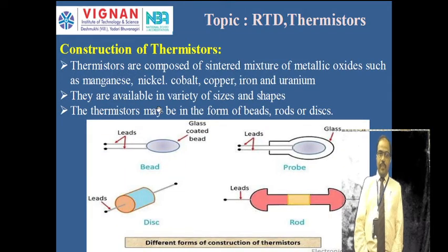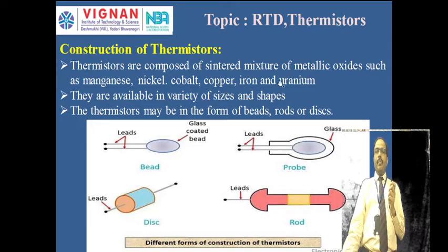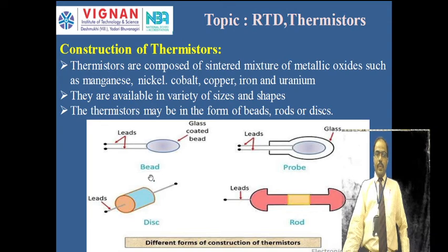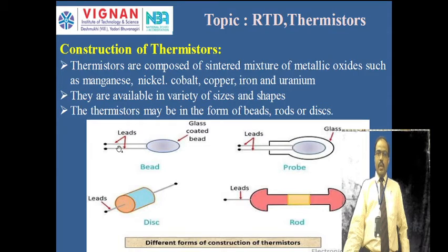Thermistors are composed of a mixture of metallic oxides such as manganese, nickel, cobalt, copper, iron, and uranium — for example manganese oxide and nickel oxide. They are available in a variety of sizes and shapes: beads, rods, probes, and discs. Each bead-type thermistor has two connecting leads. As temperature changes, the resistance of the metallic oxide material changes, which is sensed through the connecting leads.